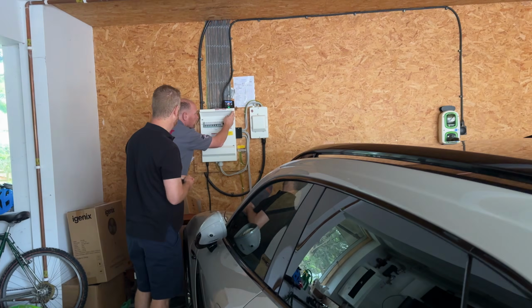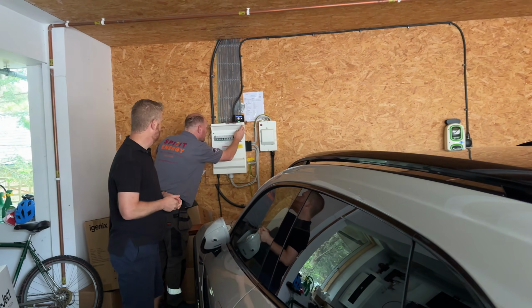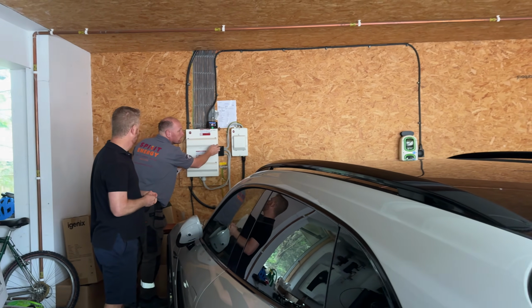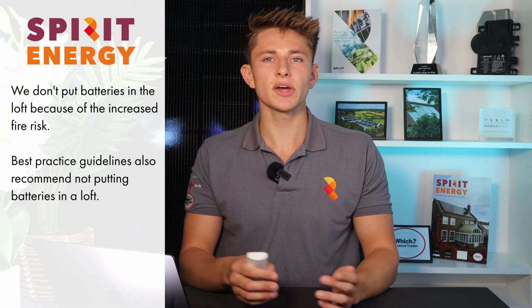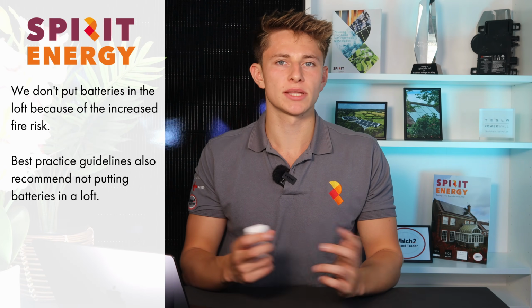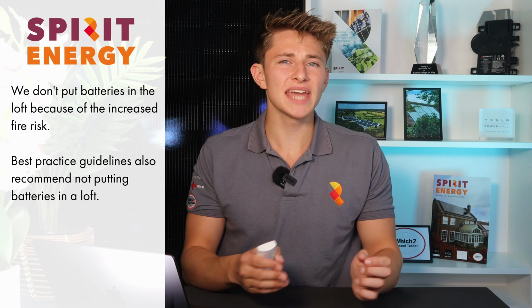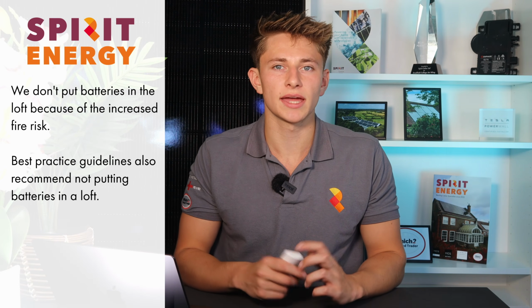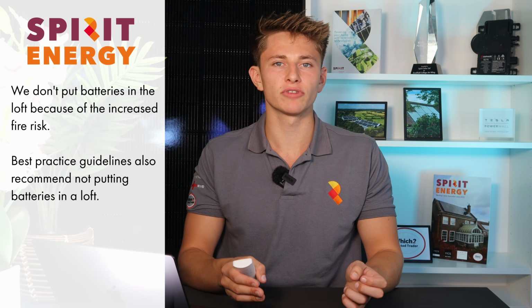The best place to put the battery is next to the incoming supply and consumer unit, especially if the battery is going to provide power cut protection to the house. We've seen some installers recommend putting batteries in the loft. However, we would never do this because of how hot lofts can get in the summer and the increased fire risk that comes along with that. Some battery manufacturers, including Tesla, won't provide a warranty unless the battery is installed on the ground floor.